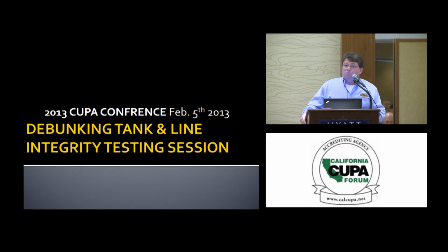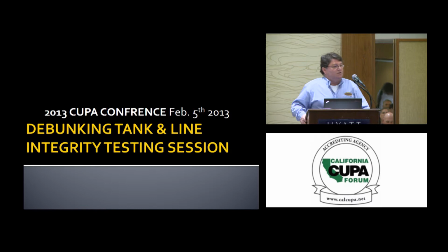We understood what needed to be done. So it came out of probability of detection. Now it's the 95-5 rule. I don't need to put the 5 up, I think you get that. But it meant that if we tested 100 tanks that were leaking 0.1 gallons per hour, I would correctly identify that 95 out of that 100 were leaking. We'd hope it'd be a lot more, wouldn't we? Truth is, it was about 98%.